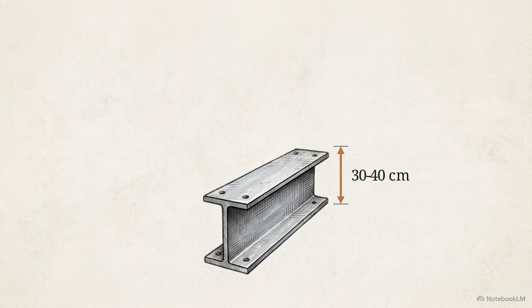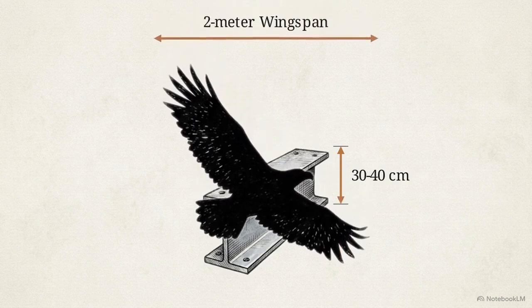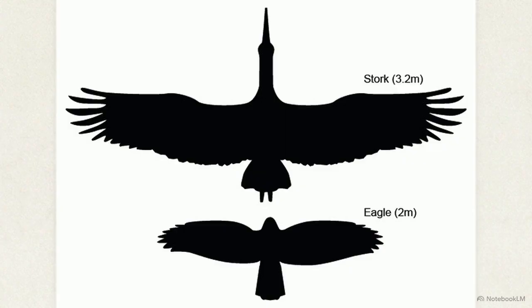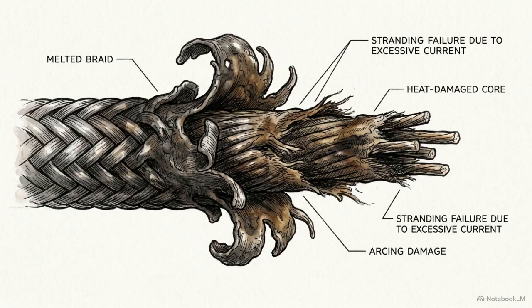Now, consider what happens when a migratory bird attempts to land or take off from this structure. With a massive 2-meter wingspan fully extended, the animal's feathers physically cross that 40-centimeter air gap, instantly completing the electrical circuit. This reference scale shows the disconnect between grid engineering and biological reality. When you contrast a 3.2-meter stork or a 2-meter eagle against the tight clearances of local power distribution, the math simply fails.